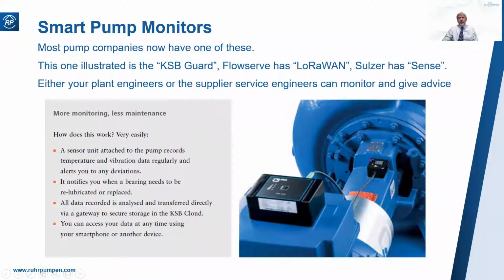You've got an accelerometer and a temperature sensor mounted here, measuring temperature and vibration on the bearing housing, sending it to a transmitter, which sends it directly to the cloud, where it will be automatically analyzed, and you'll be sent an alarm if they recommend you have to change the bearings or something of that sort. Sometimes they are monitored by experienced machinery engineers at the pump vendor, and they might get in contact with you and talk about your pumps.